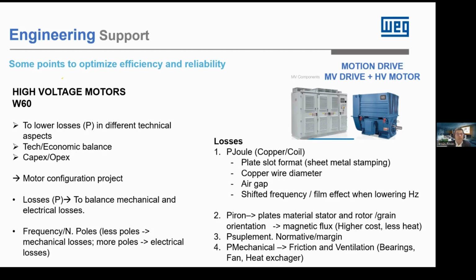When it comes to achieving the best efficiency, it's basically a matter of reducing losses, okay? Less losses, more efficiency, that's clear. So the number of poles and the frequency are also taken into account because they have influence on these losses, mechanical and electrical losses. If we go to this area, to the losses, I try to summarize the electrical effects and losses. For instance, the Joule effect losses. You have to look at the coil, the plate slot format. The metal sheet is stamped in the metal plates to house the coils. You have to consider the shape, the model, even the copper wire diameter, the air gap, or even the skin effect that happens when you lower the frequency. So this determines the Joule effect losses.